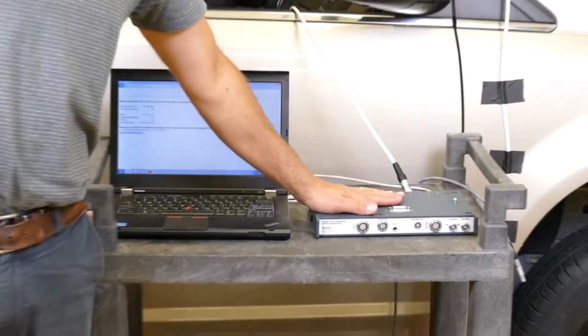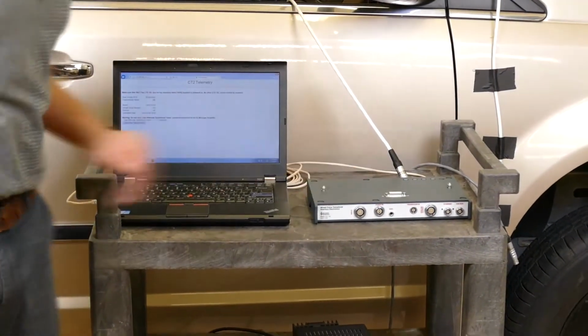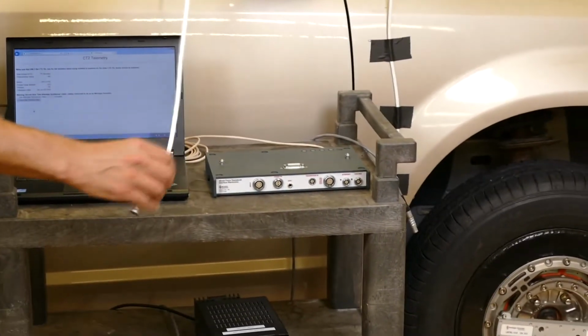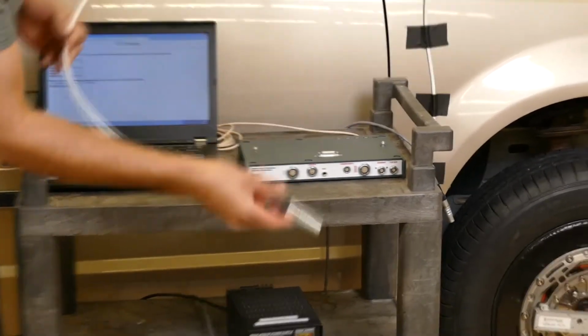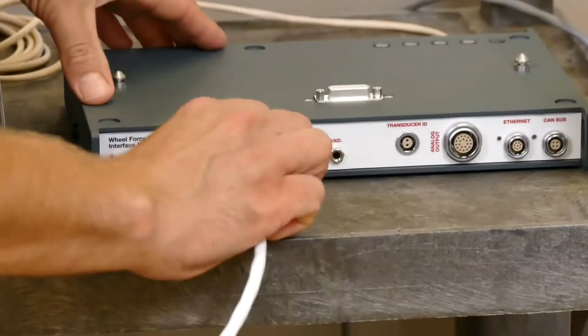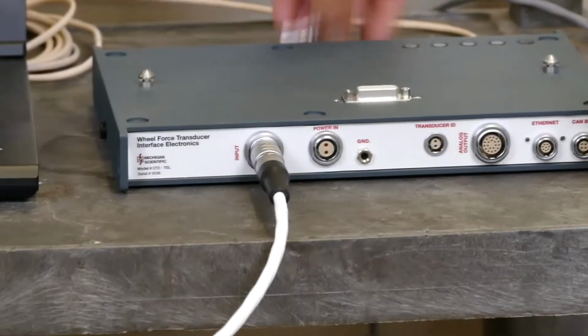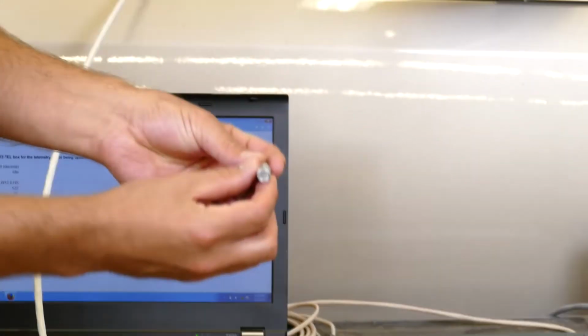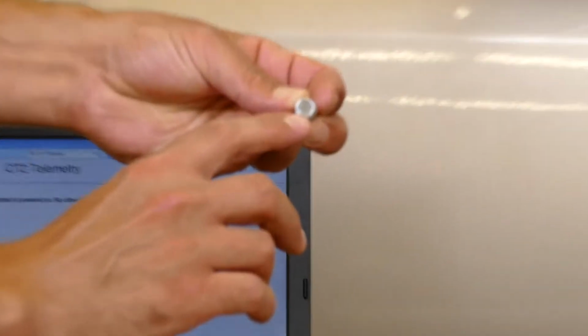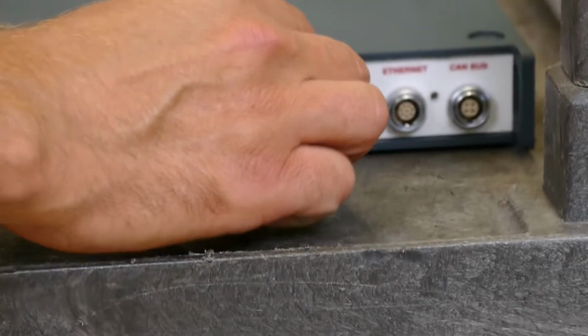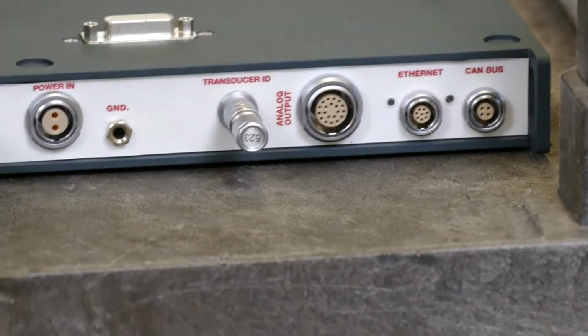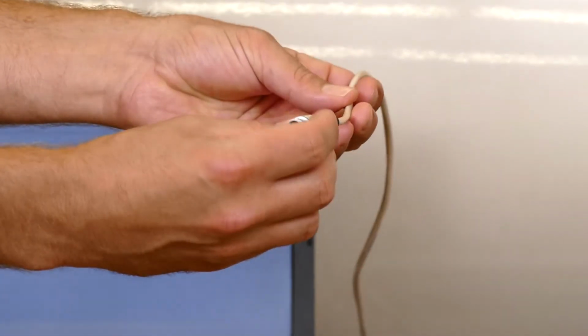Next step is to connect the cables to the CTS telemetry box. This is the cable connected to the telemetry stator. That goes into the input connector. And then we have to connect the dongle. So this dongle has a serial number that matches the serial number on the transducer. So we plug that into the transducer ID dongle connector. We're also going to connect the power cable and the Ethernet cables for connection to the laptop.